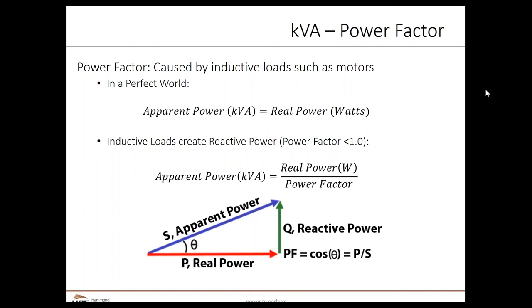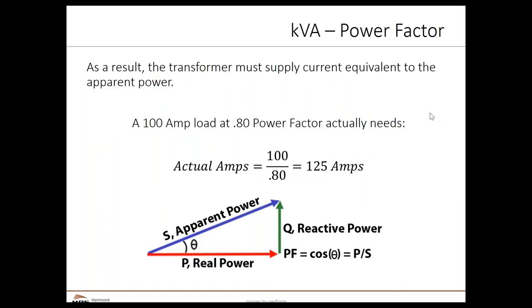Let's look at an example of how it's calculated. A 100-amp load at 0.80 power factor actually needs 125 amps based on the calculation. The transformer in this case has to be sized for 125 amps, not 100 amps.